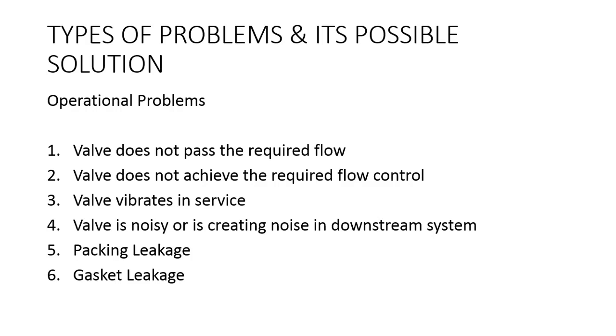Second, valve doesn't achieve the required flow rate. Here what we can do is check whether the problem is permanent or temporary first. If it is permanent, then the valve is surely undersized or oversized. If it is temporary, then there is some instability in the valve, the valve is sticking, or there is some misoperation.